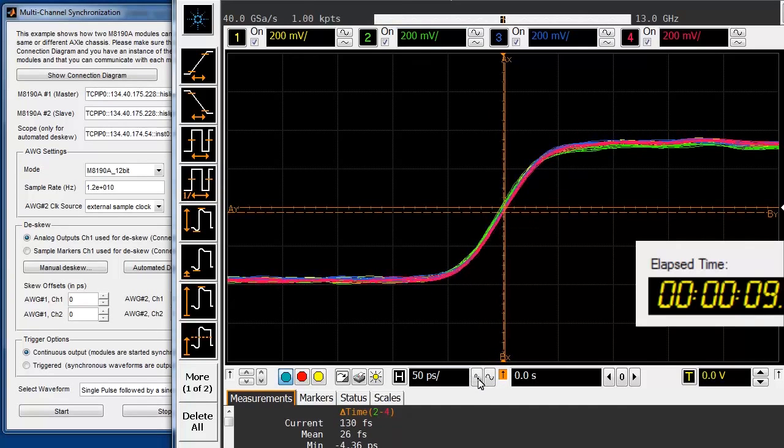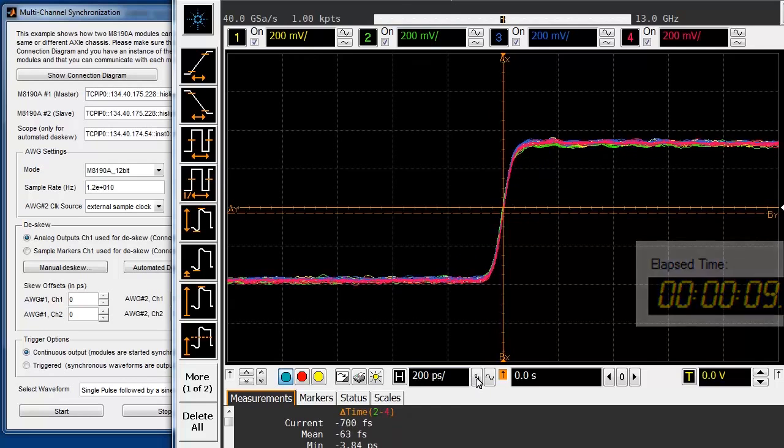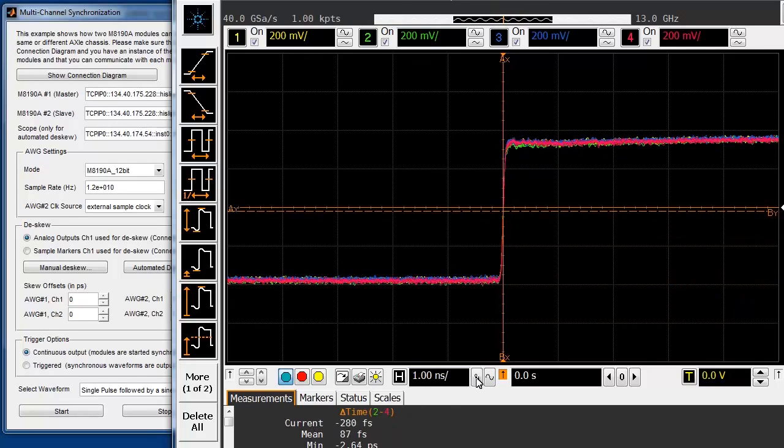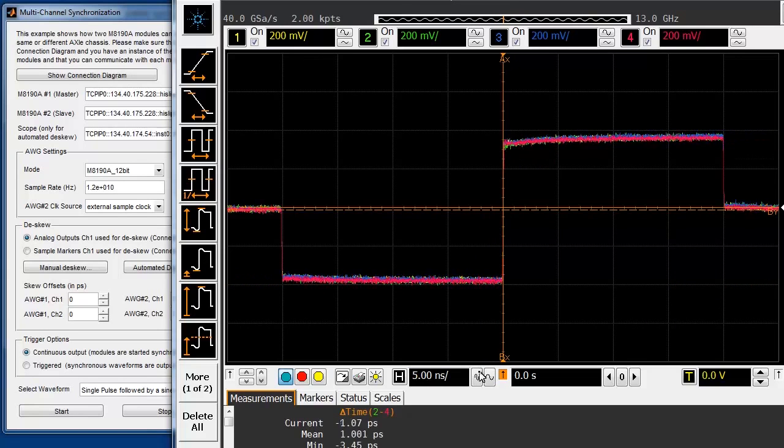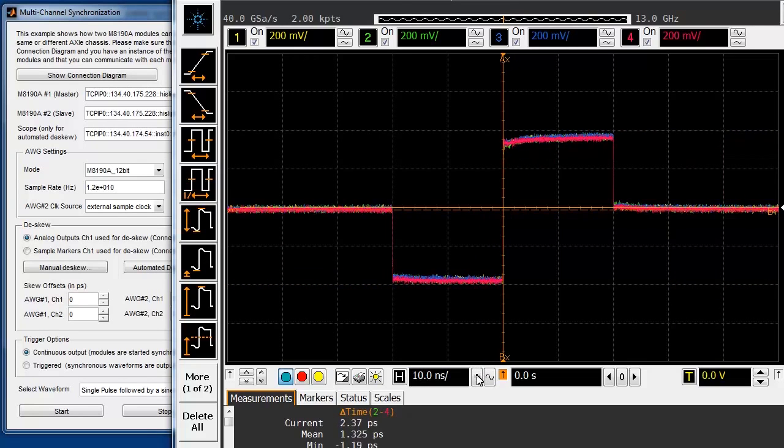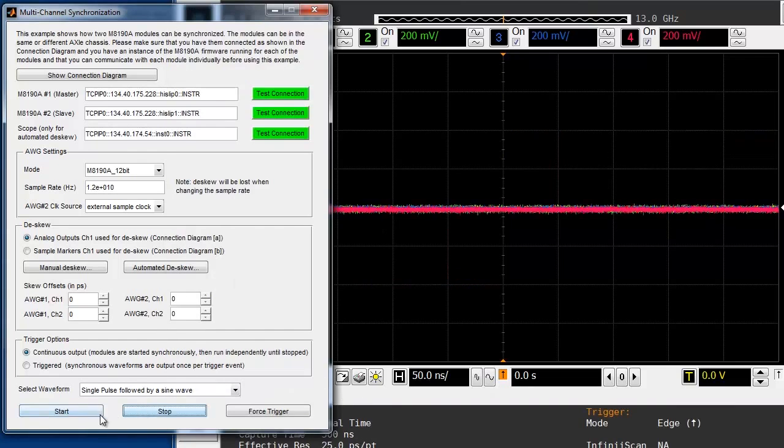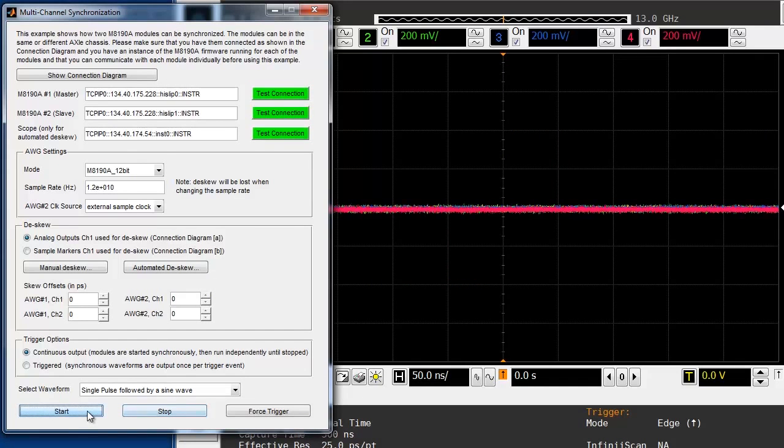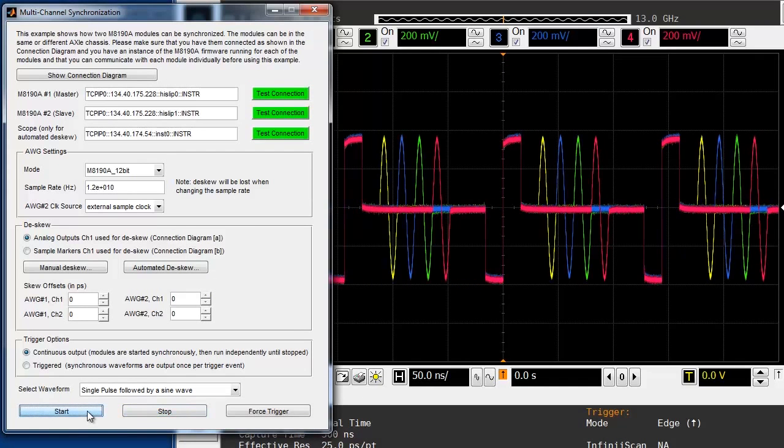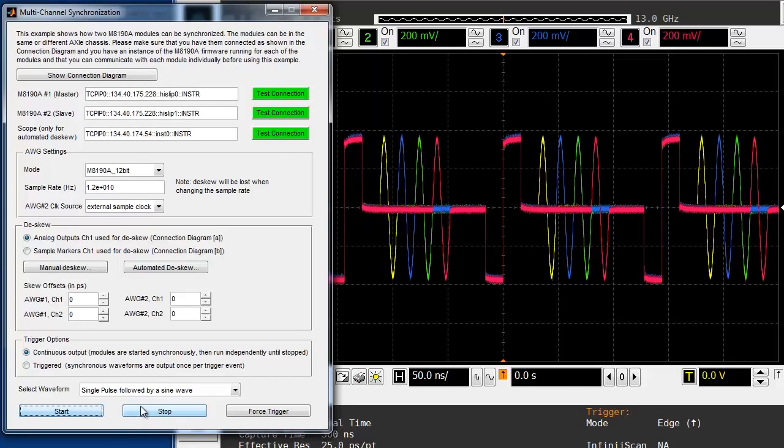Once the alignment has been performed, the signal generation can be stopped and restarted without losing the synchronization. You can also stop the generator, load new waveforms, and still maintain the synchronization.